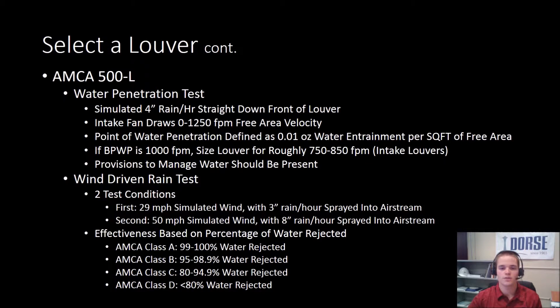This only matters for intake louvers since exhaust louvers will be blowing air out of them — you only need to be concerned with the pressure drop. Regardless of how you size the louver, you will want to make sure there are provisions to manage water collecting inside of the louver. The other test is the wind-driven rain test. There are two test conditions. The first is a 29 mile per hour simulated wind blowing towards the louver with 3 inches of rain per hour being sprayed into the airstream. The next and more extreme condition is a 50 mile per hour simulated wind with 8 inches of rain per hour. The louvers are then graded based on their effectiveness in rejecting the water, from class A being the best to class D being the worst.